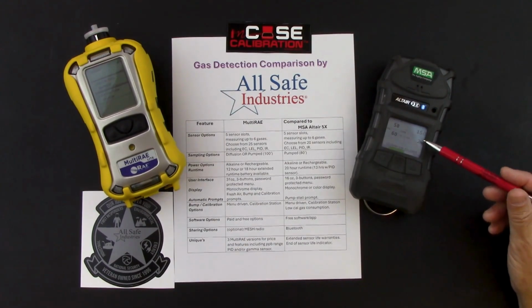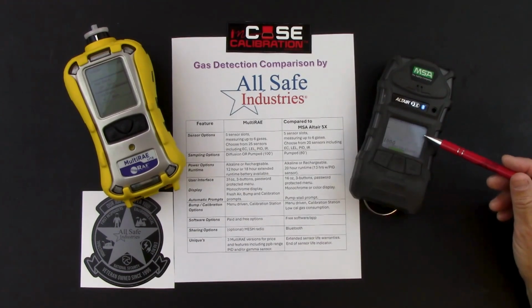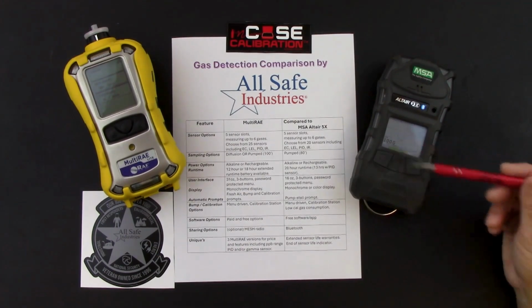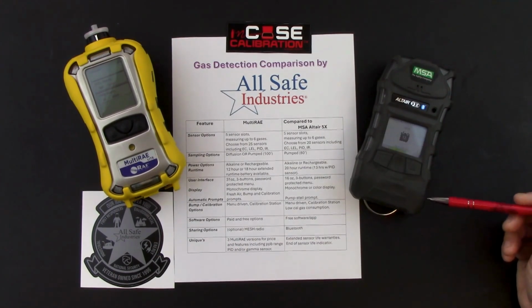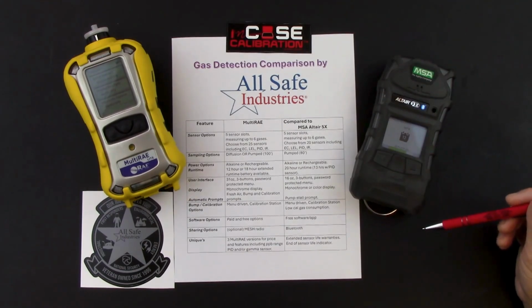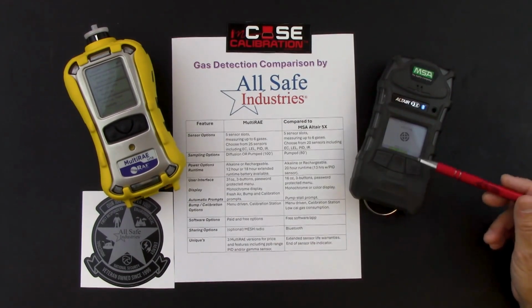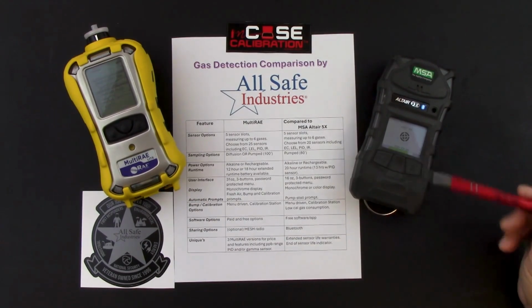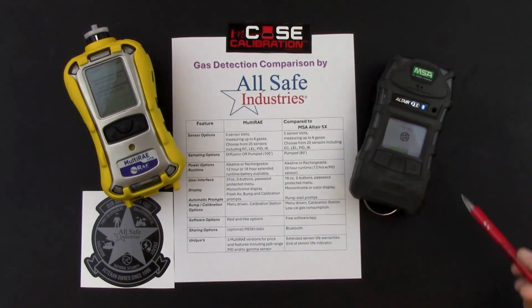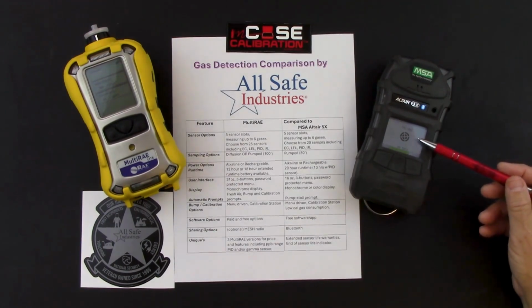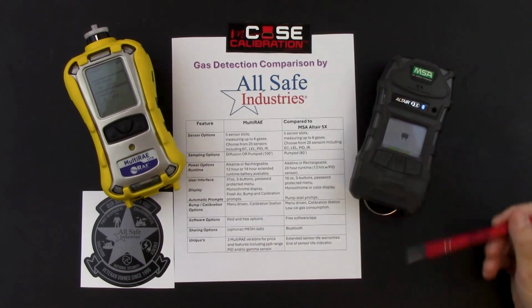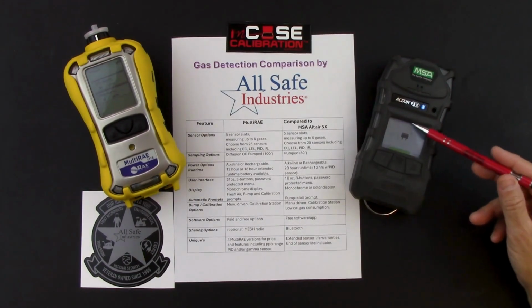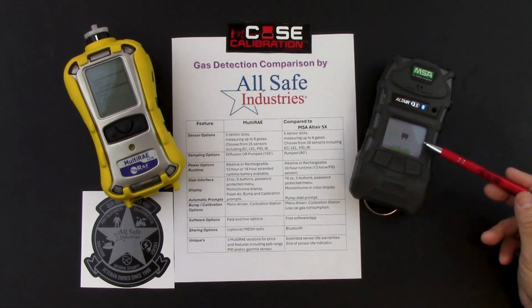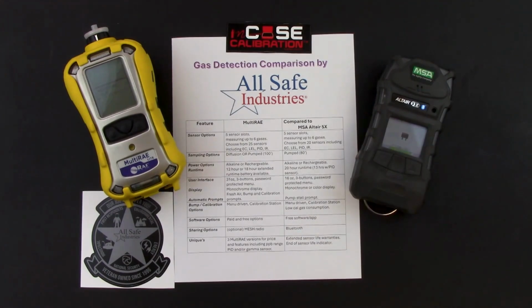There, of course, are my calibration gas settings, including for the PID, my time and date, the last time this instrument was calibrated, when the calibration is going to be due, so it's a 60-day calibration sequence here, and then finally I'm to the last screen as I'm waiting for those sensors to finish warming up.